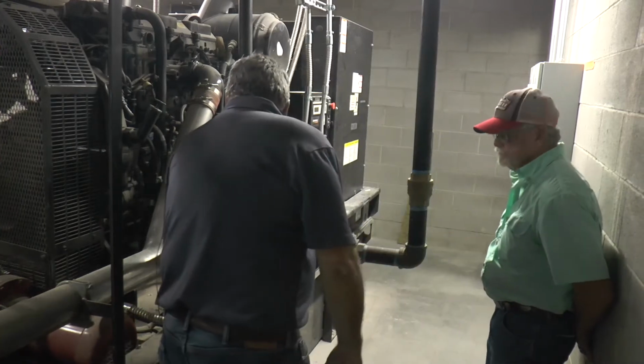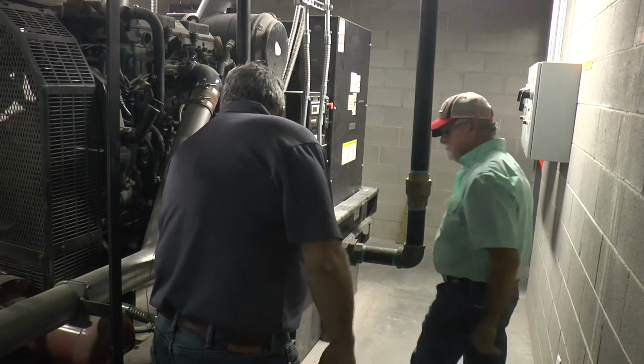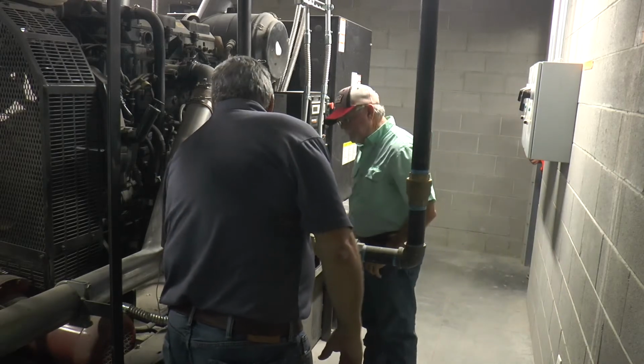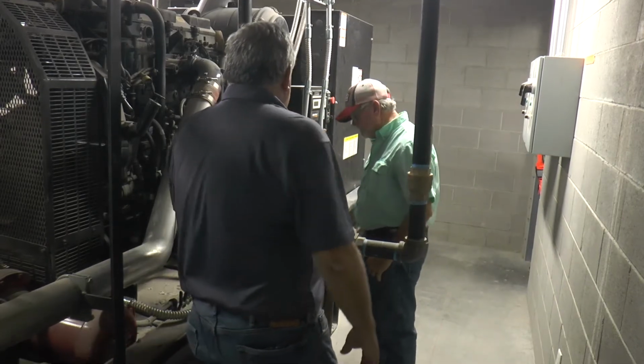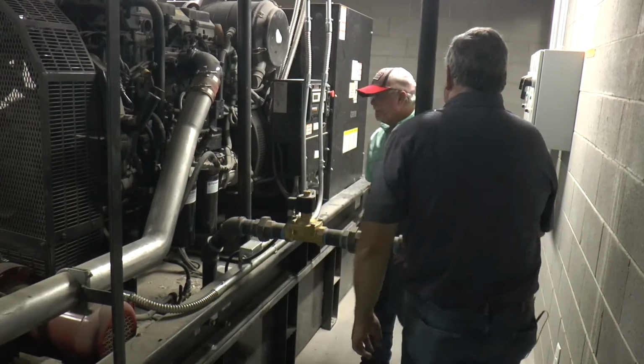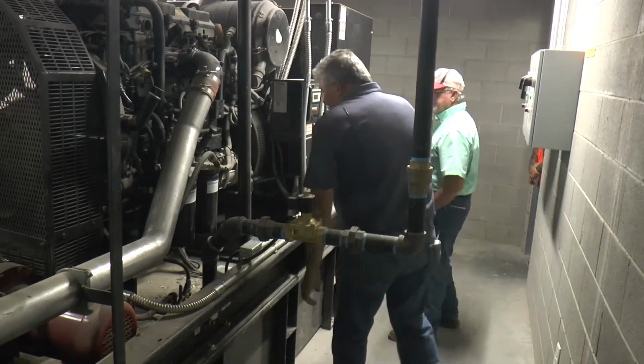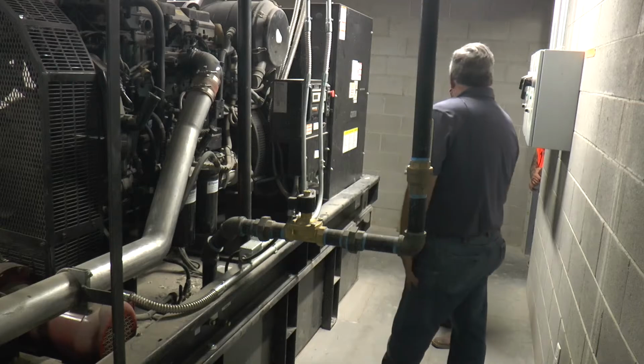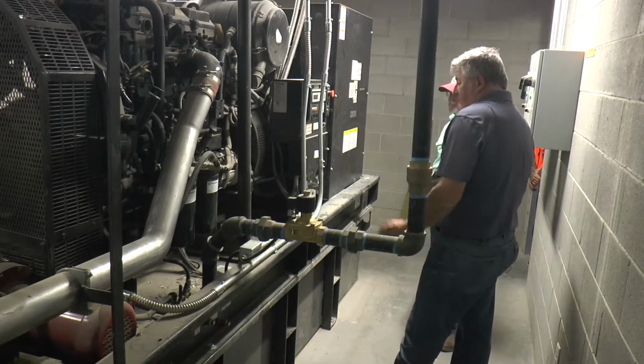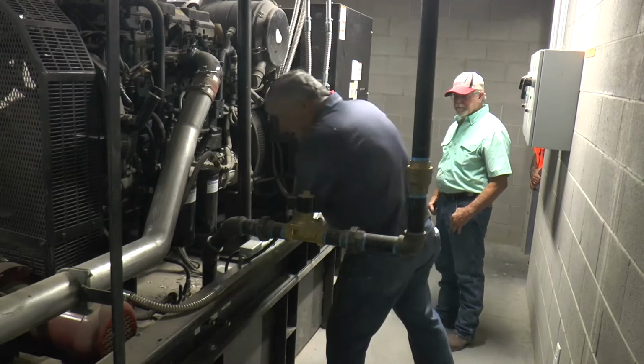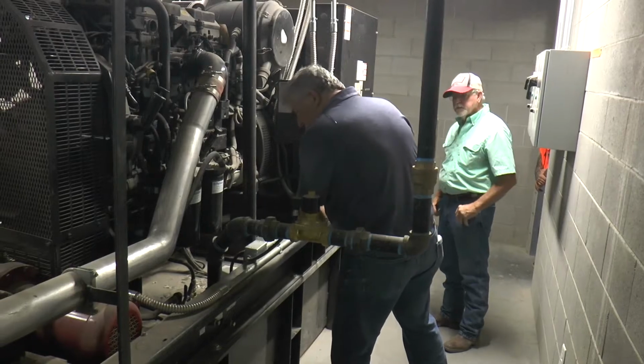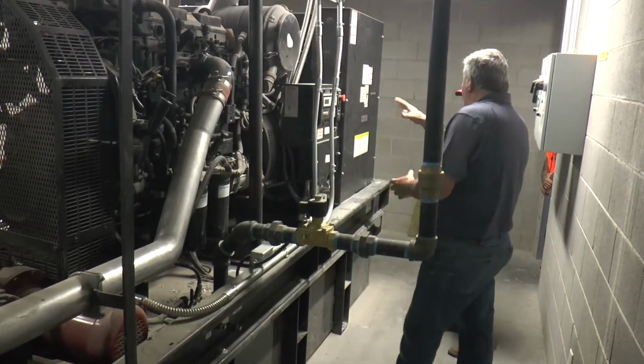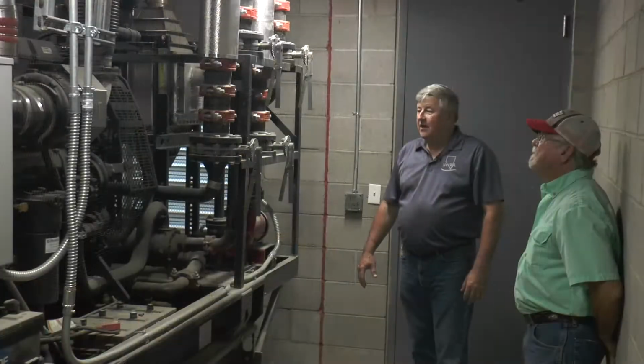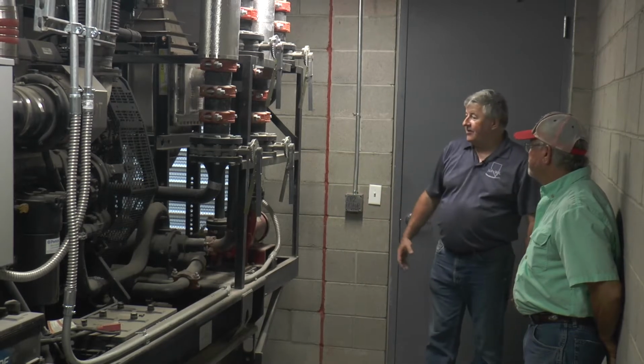You have your supply and return lines for your fuel and a fuel level gauge. Visually one here, and then you have a percentage gauge on the controller. City of Phoenix limits us to filling the tank to 95%. So, they did the load bank test and everything else, and you're just a little over 3/4. So right around 80-85%.